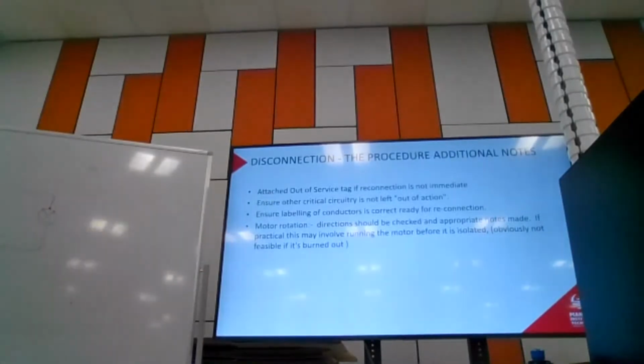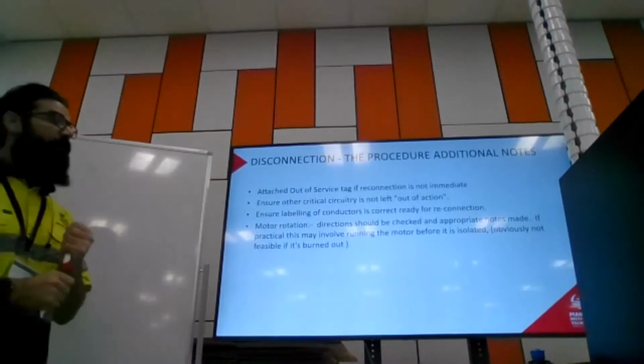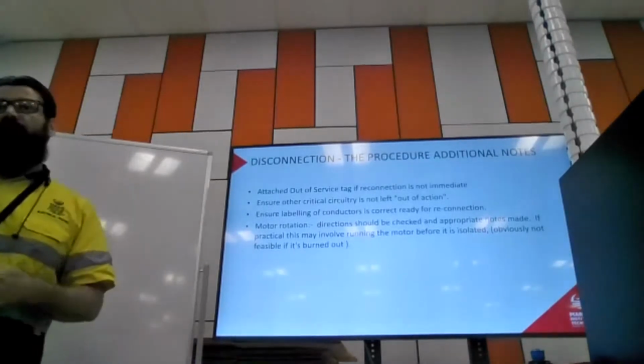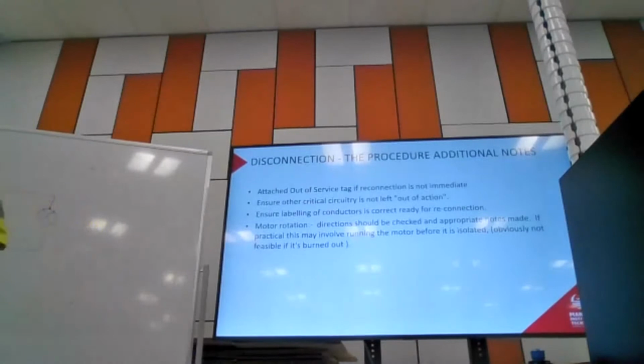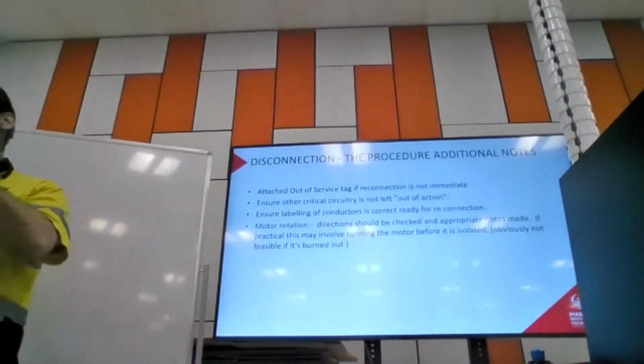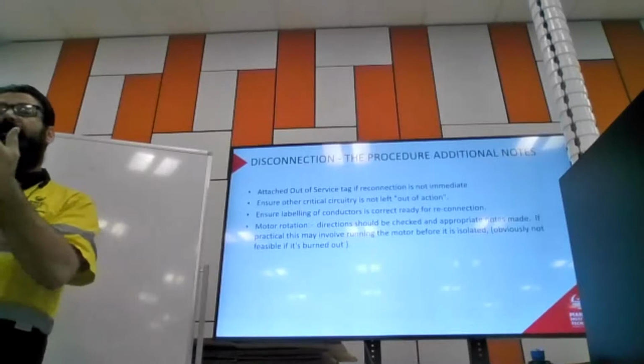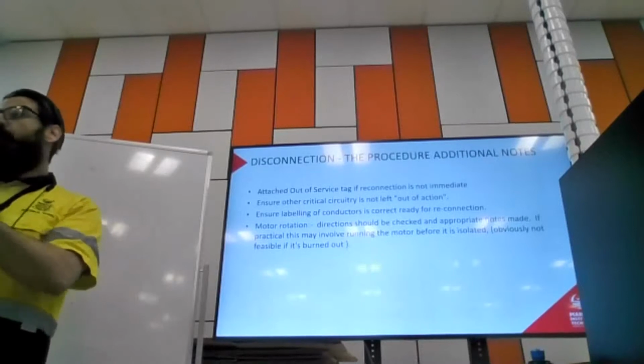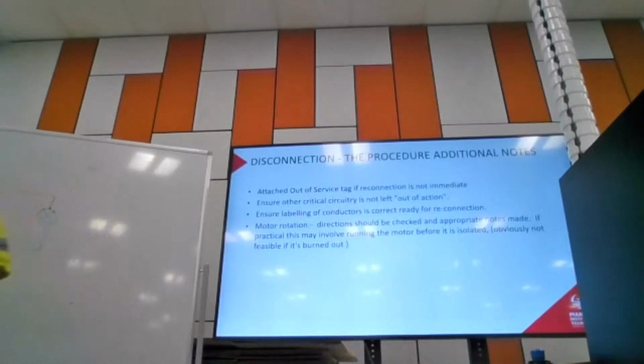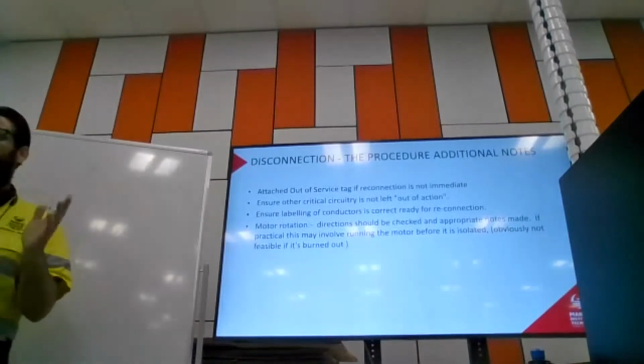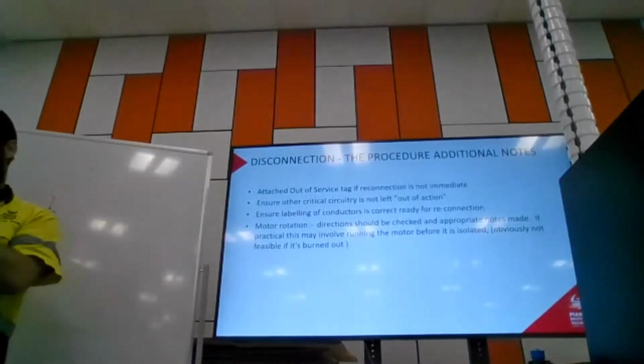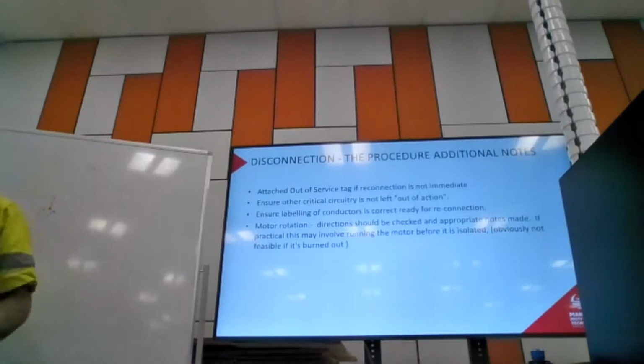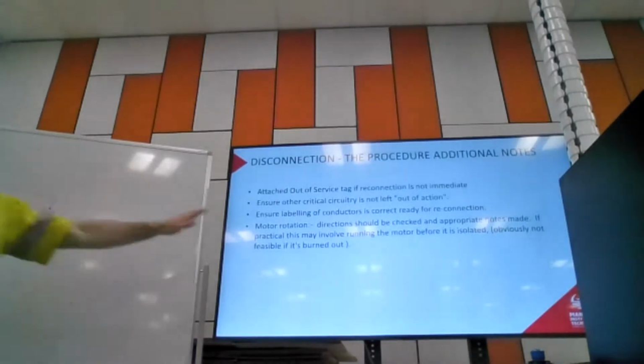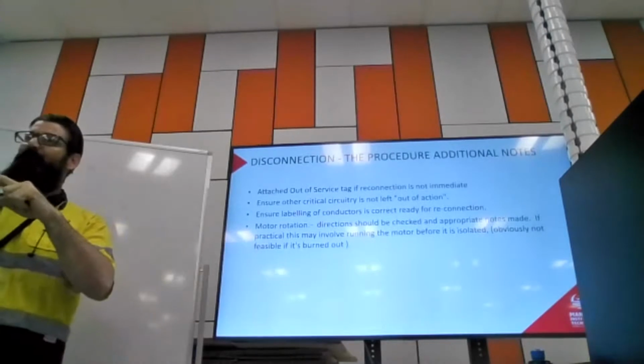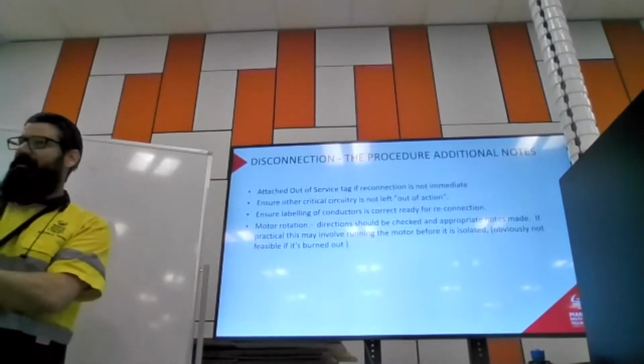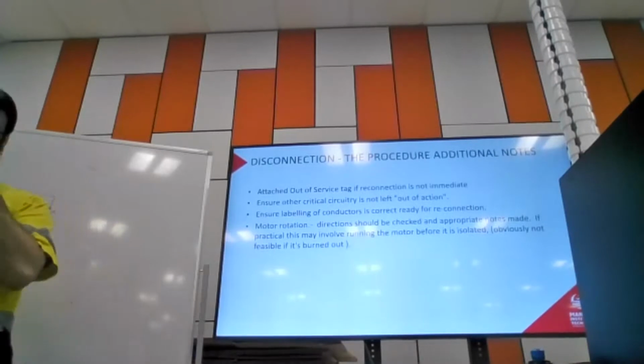Motor rotation - direction should be checked and appropriate notes made. If practical, this may involve running the motor before it's isolated. Obviously not feasible if it's burnt out, or maybe if there's some other fault there. With a three-phase motor in particular, the only thing that controls the direction of rotation is the polarity of my three phases. If I switch one, the motor's going to run in the other direction, which is awesome, because it means you can switch a motor really easily - just switch any two of the three phases and it rotates the opposite direction. Fantastic. But if I'm removing a motor to work on it, I should check which way it rotates first, and make sure I know what the connections are, so when I put it back in, it's not going to run backwards.